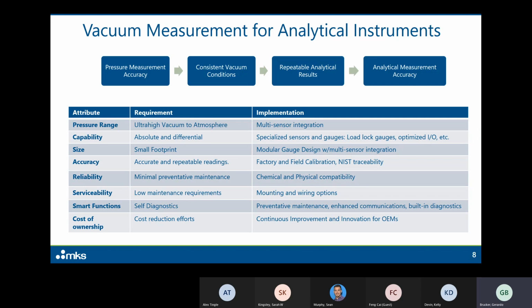Of course, the analytical industry wants serviceability. Low maintenance requirements are very important. There are also very specific gauge mounting and wiring requirements developing in the industry, and we have to be able to take care of all of those. There is an increasing demand for smart functions and built-in self-diagnostics. It's good to know that something is about to break before it breaks. Some gauges eventually will fail. That's just the nature of the technology, just like other parts of your analytical instrument. And it's good to know in advance, before the failure happens, that it's about time to do a PM or a service.